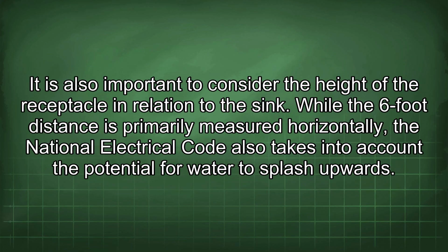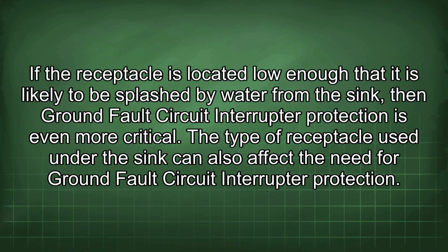It is also important to consider the height of the receptacle in relation to the sink. While the 6-foot distance is primarily measured horizontally, the National Electrical Code also takes into account the potential for water to splash upwards. If the receptacle is located low enough that it is likely to be splashed by water from the sink, then ground fault circuit interrupter protection is even more critical.